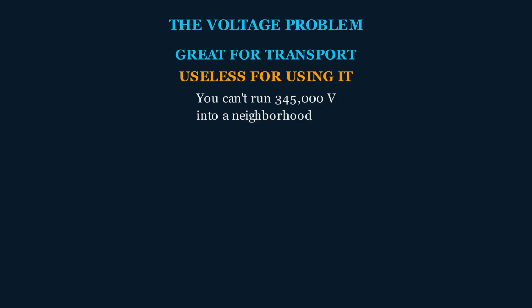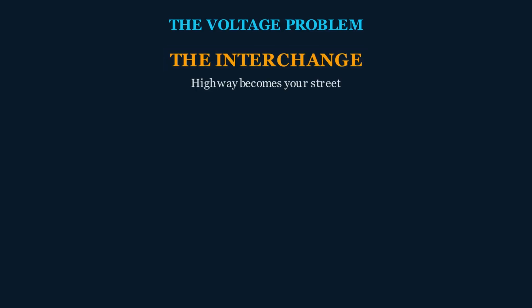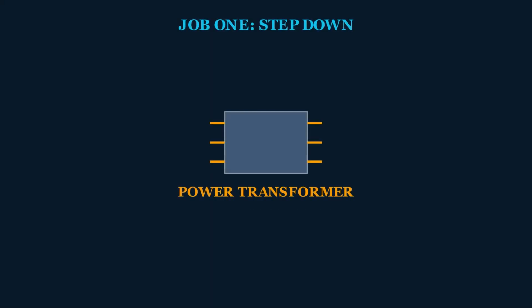survive. So there's a fundamental mismatch. The grid moves power at a voltage that's great for transport and lethal for delivery. Something has to bridge that gap. Something has to take the high transport voltage and bring it down, in stages, to the modest voltage that can safely run down your street and into your home. That something is the substation. Think of the transmission grid as an interstate highway moving traffic at enormous speed, and your street as a quiet residential road. The substation is the interchange, the off-ramp where the interstate slows down and becomes something a neighborhood can actually use. So that's job one, changing the voltage.